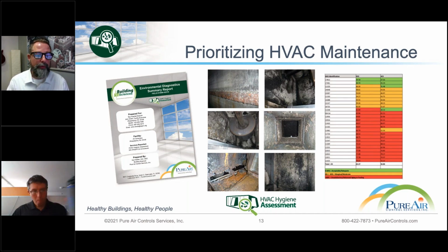A certain kind of mold, as you can see in these pictures, that often grows on fiberglass in single wall units that, over time, get damp, sag, start to break down, and become very porous. Dust gets trapped in there, mold starts to grow, and it can become a real issue. A lot of times this is post-filtration, so if this mold produces spores, it's going to blow. Some of it will clog and foul the coils, and some might make it through into the ductwork and into the occupiable space. I think these pictures are a good example.